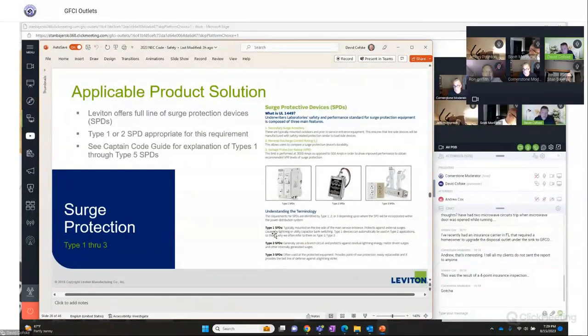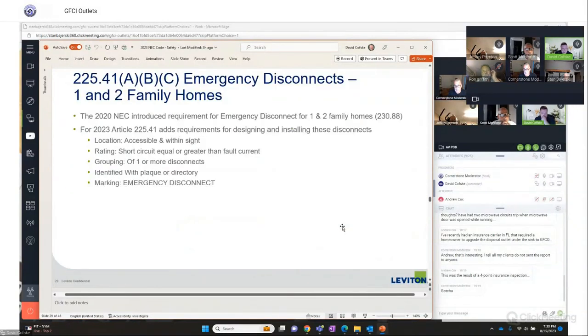So when you get into surge protective devices, they basically break it down into categories of type 1, 2, and 3. Type 1 is an actual circuit breaker that is a whole home surge breaker. Type 2 is a unit that you can actually wire into your load center. And then type 3 is basically surge receptacles, or the plug-in strips. But when you get to code, the inspectors are really looking for type 1 and type 2 surge in the home. It might be something to recommend to people because with everything being electronic, there's more problems with noise and surges coming into the house causing problems, and this will dovetail into that microwave situation when we get to it.